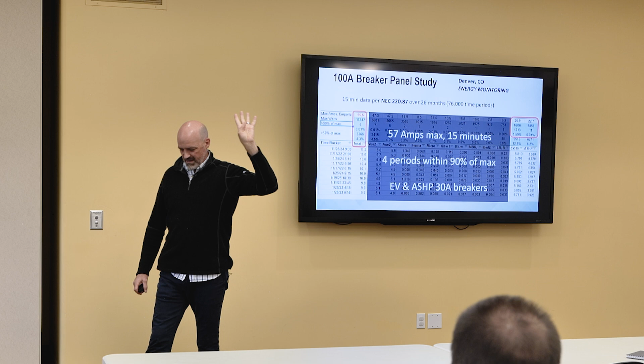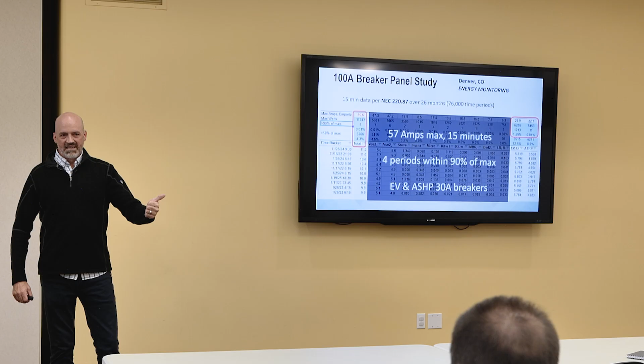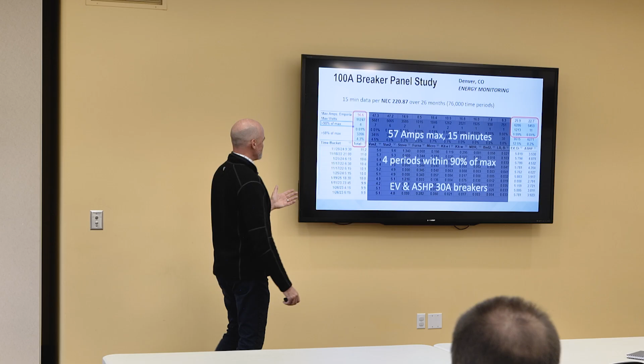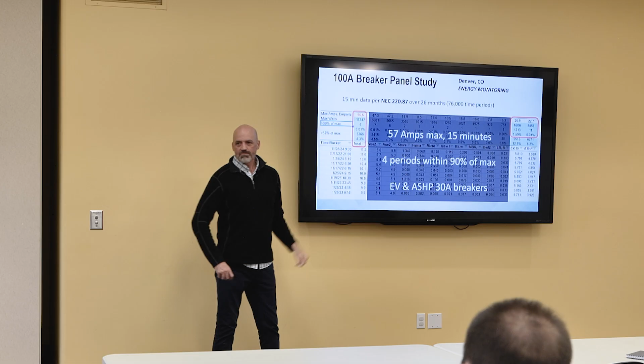One more thing on here. This line right here, I've got highlighted for a reason: 90% of max. That means there are only 4 more 15-minute data periods over that 26 months within 90% of that 57 amps. So not only does it not happen, it almost always never happens. This is 0.01% of the time it's within 90% of that peak.